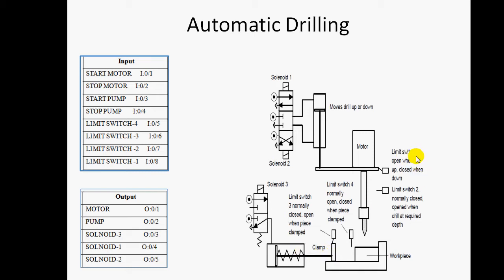Solenoid valve three is for clamping purpose. We also require four limit switches. Limit switch one identifies the drill-up position. Limit switch two identifies the required drilling depth. Limit switch three identifies the unclamp position of the workpiece, and limit switch four is for clamping of the workpiece.